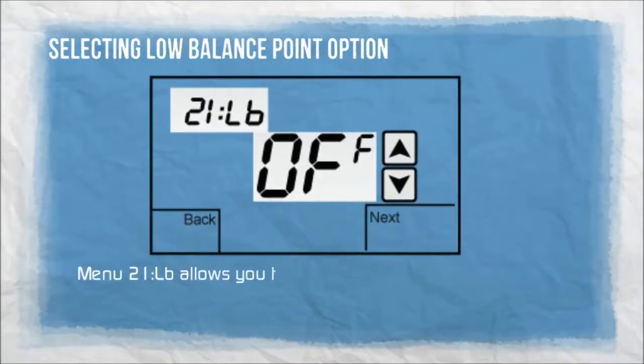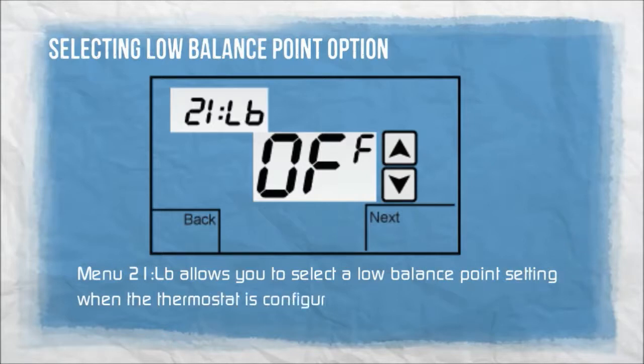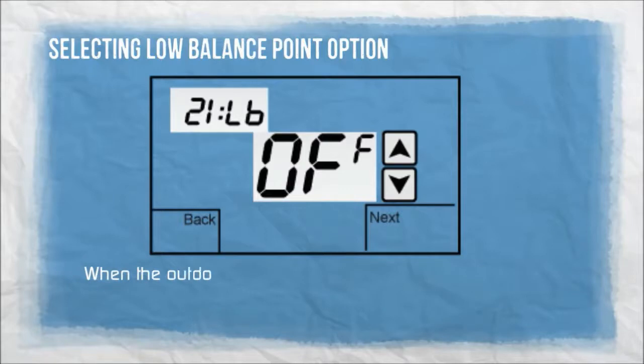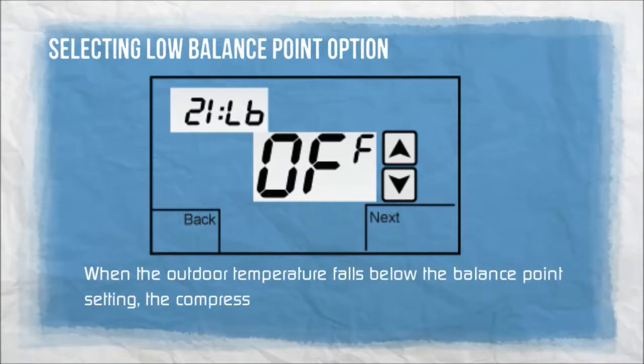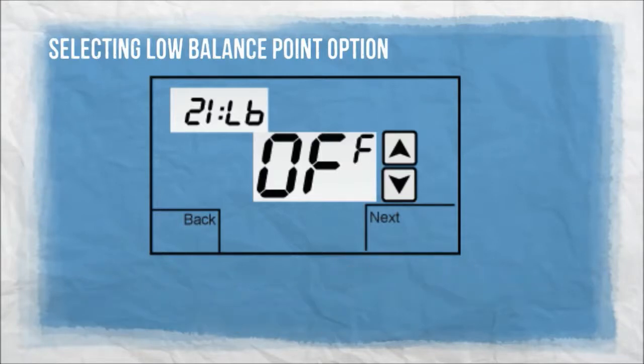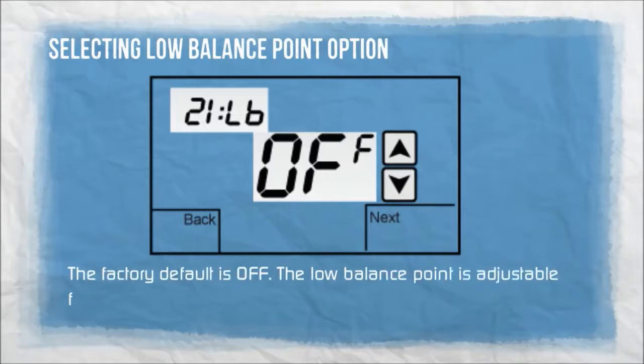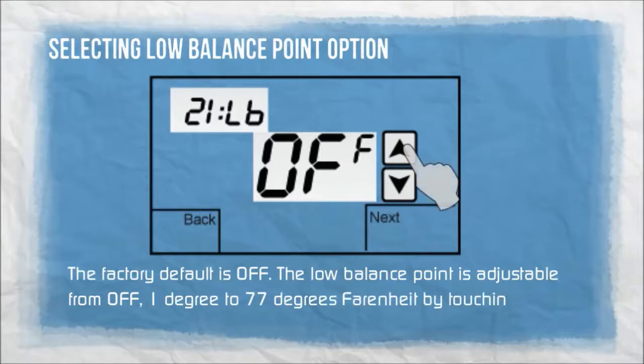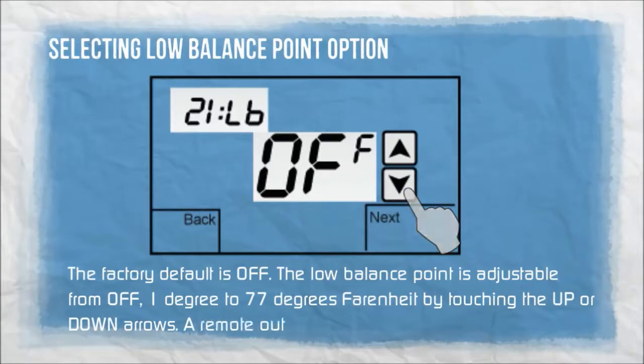Menu 21LB allows you to select a low balance point setting when the thermostat is configured for heat pump or fossil fuel. When the outdoor temperature falls below the balance point setting, the compressor is locked out and only auxiliary heat or fossil fuel is used for heating. The factory default is OFF. The low balance point is adjustable from OFF, 1 degree to 77 degrees Fahrenheit. A remote outdoor sensor must be installed.